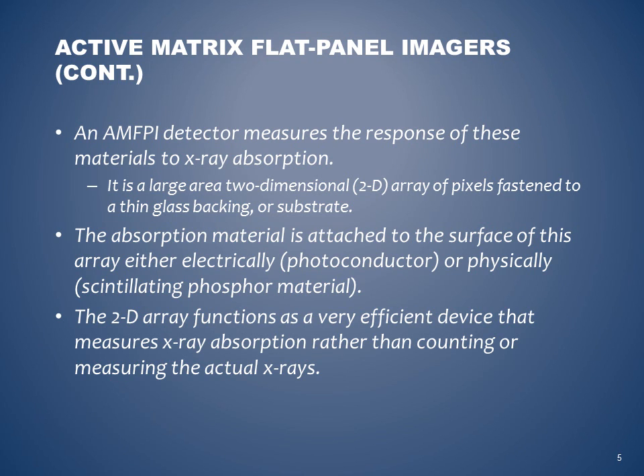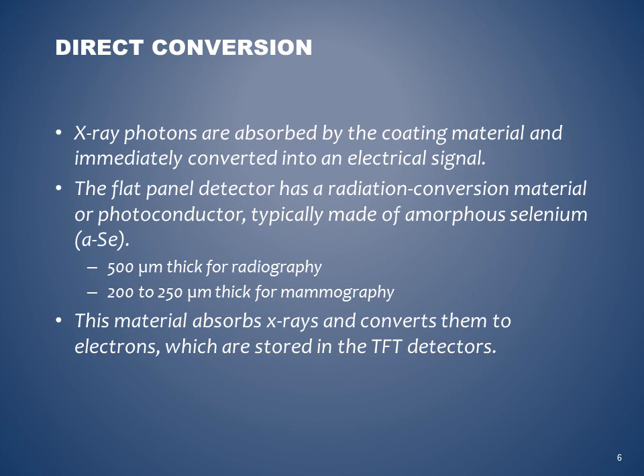An AMFPI detector measures the response of these materials to X-ray absorption. It is a large area, two-dimensional array of pixels fastened to a thin glass backing. The absorption material is attached to the surface of this array, either electronically, which is the photoconductor, or physically, which is the scintillating phosphor material. The 2D array functions as a very efficient device that measures X-ray absorption rather than counting or measuring the actual X-rays. Direct conversion. X-ray photons are absorbed by the coating material and immediately converted into an electronic signal.